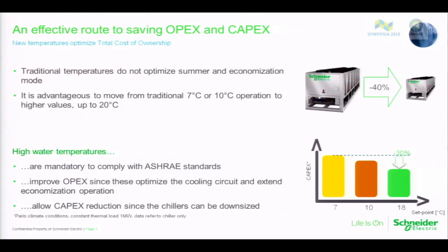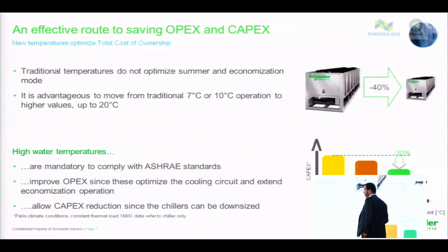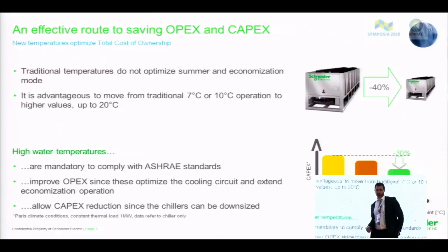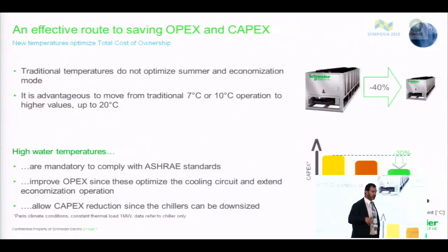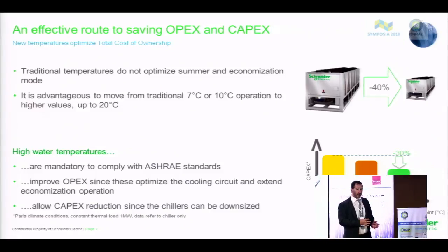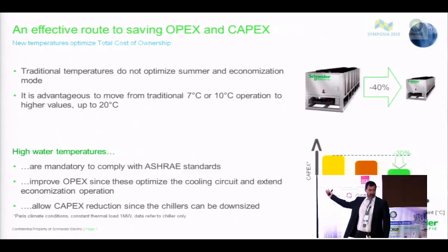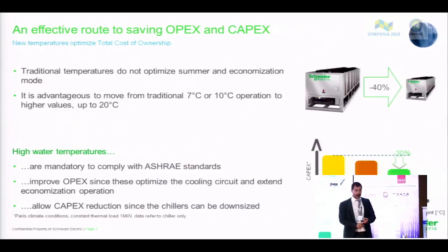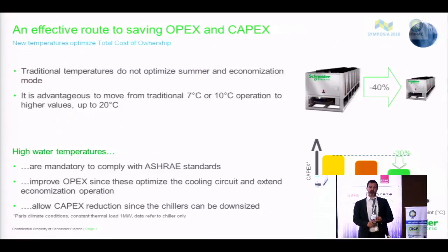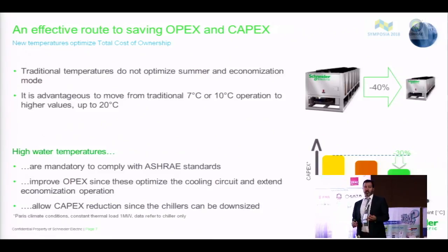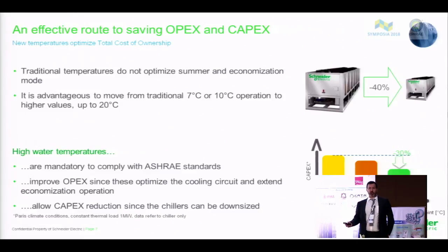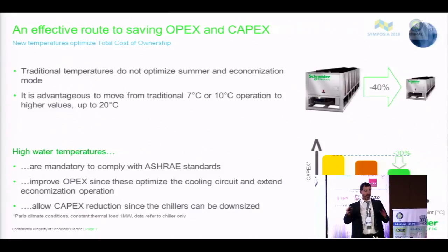Because when you design a data center at 25, 26 discharge, let's take for example the chilled water system, this means that the chiller can be designed to operate at water up to 20 degrees Celsius. There are many installations that are working at 20 degrees Celsius discharge on the chiller. And of course, when you move the temperature from the traditional 7, 10, 15 to 20, it means that the chiller is smaller. So this means cheaper. This means that the electrical infrastructure is cheaper, and it is more efficient. The golden rule says that for each degree of increased water temperature, the chiller is able to provide 3% more capacity. It's not perfectly true, but it is a good number.